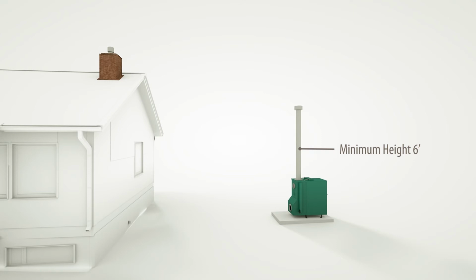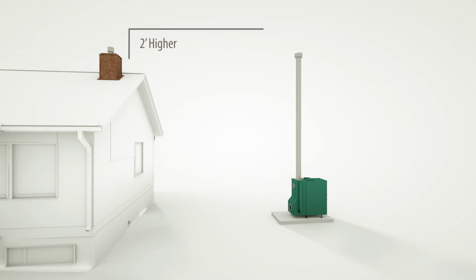If the unit is closer than 10 feet to the home, the 10-2 rule must be followed. The top of the chimney must be 2 feet higher than any structure that is within a 10-foot radius. See your owner's manual for additional details. After installing the required chimney sections, install a chimney cap to prevent rain from entering the furnace. Additionally, be sure to seal the outer edge of the chimney to the top of the furnace to keep water out of the furnace.